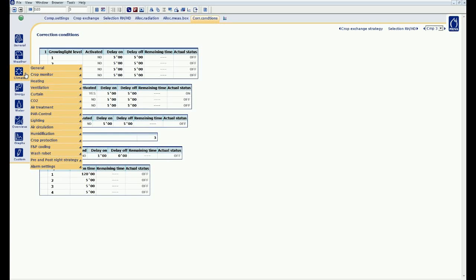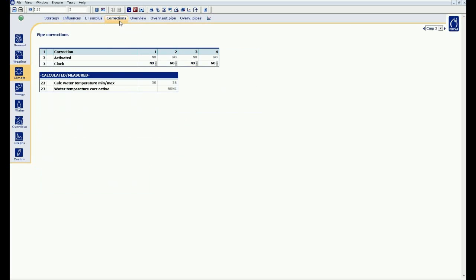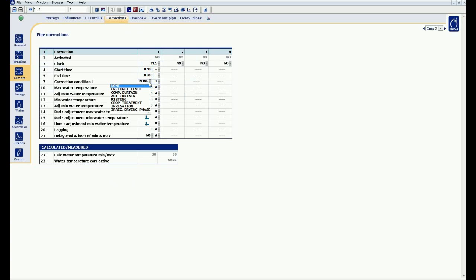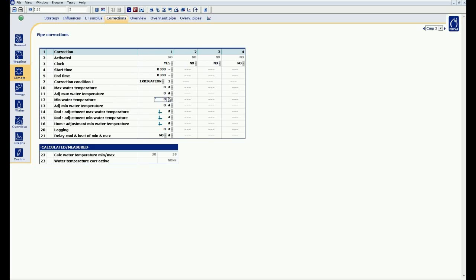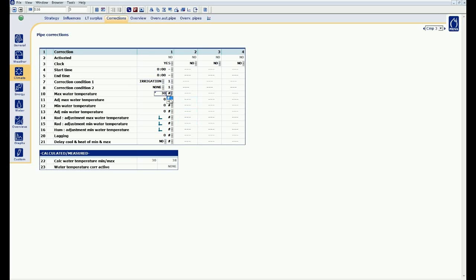I go to the pipe settings and click corrections. I activate the first correction period, then I go to the correction condition 1 and choose irrigation. Throughout the correction, I want the maximum pipe temperature of 30 degrees during irrigation. The equal sign means that I want to take over this value in my strategy. In other words, as soon as I am going to irrigate, the condition is true and a maximum pipe of 30 degrees is used.